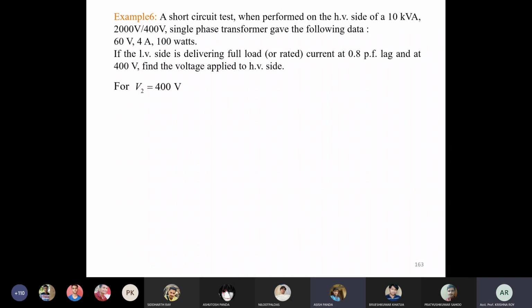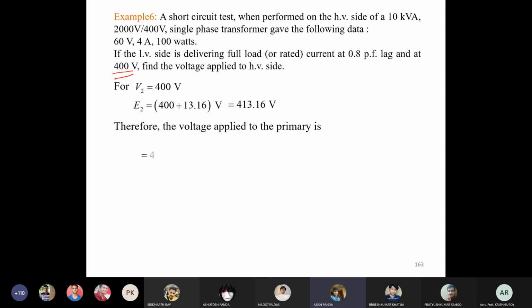Now calculate E2. V2 is given as 400 volt, because the low voltage side is supplying some load at 0.8 power factor lag at 400 volt. So the output voltage V2 is 400 volt. For that, what will be the value of induced EMF on the secondary or low voltage side, that is E2? E2 is 400 plus 13.16. Now using the turns ratio, calculate the supply voltage to the primary side. The primary applied voltage will be this into the turns ratio, which is 2065.8.